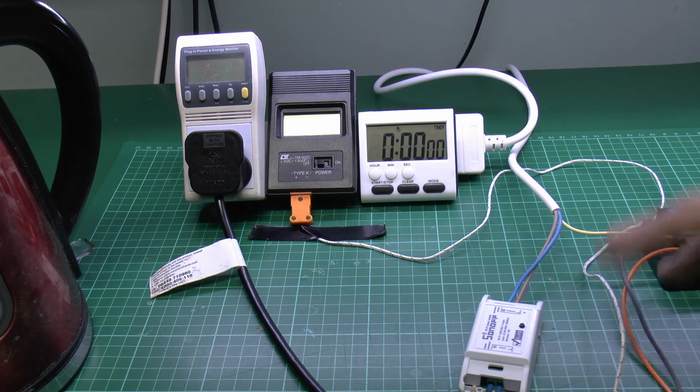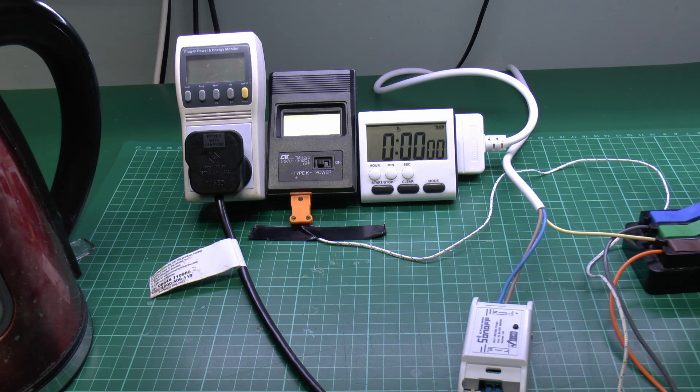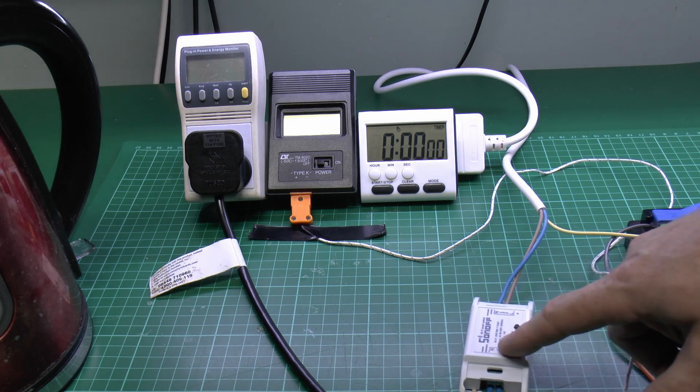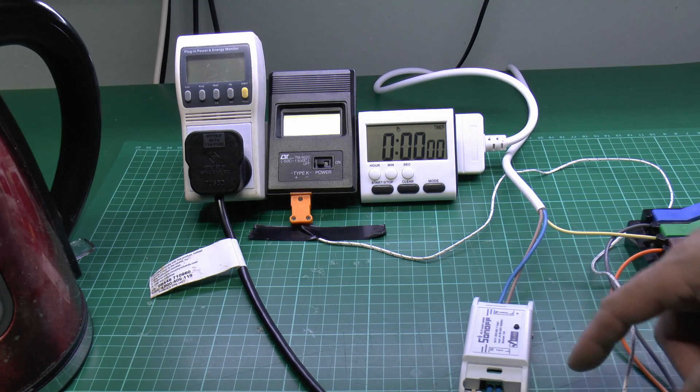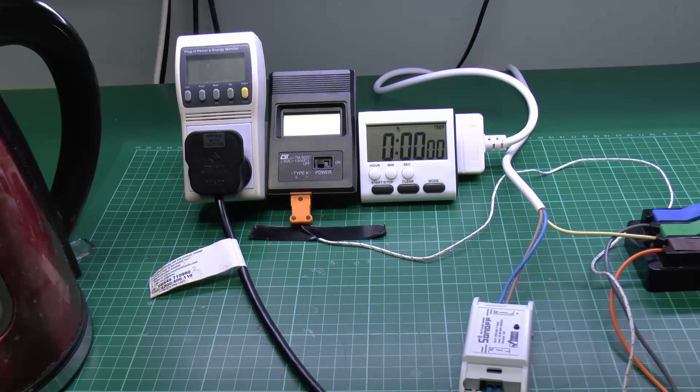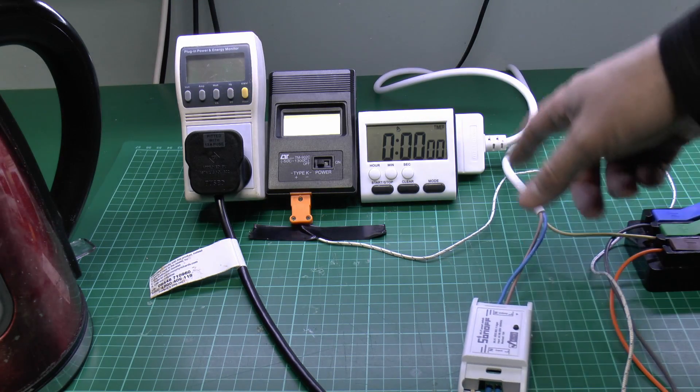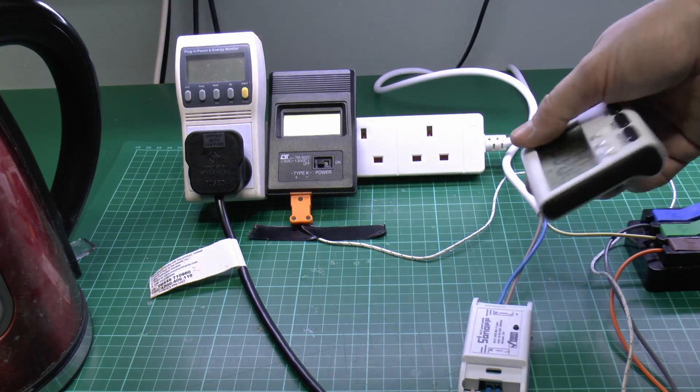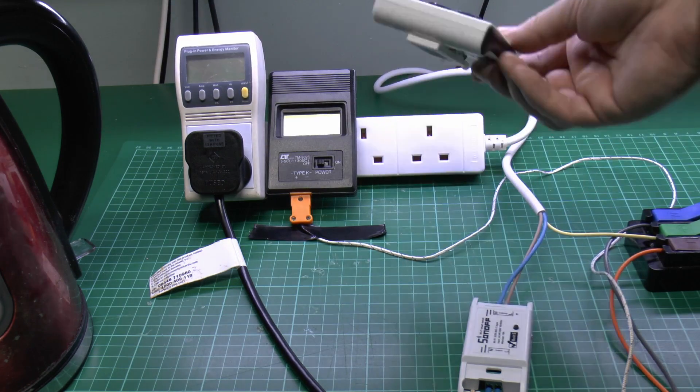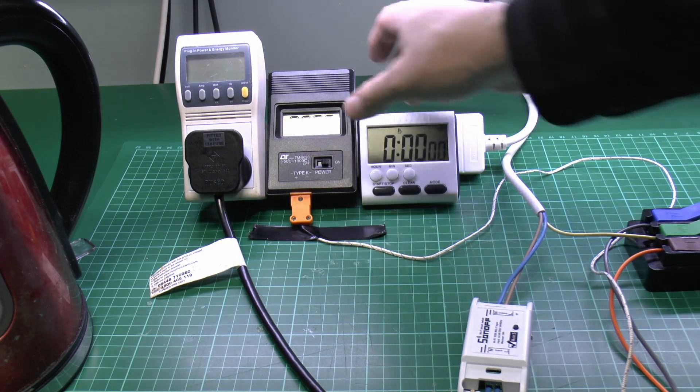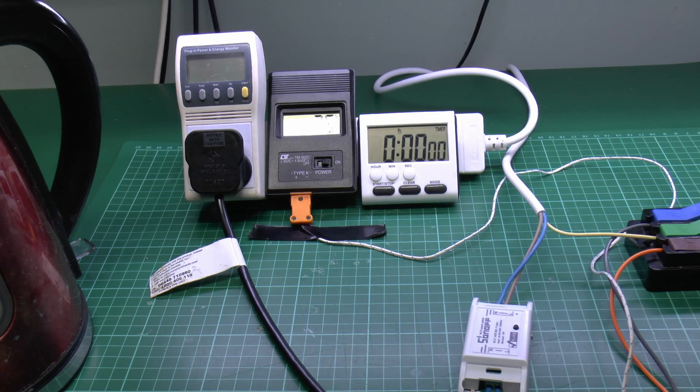Now here's the test arrangement. Power coming in here on this connector block, line and neutral just go into the device here. And the earth actually comes directly there because, as we saw previously, there's no earth connection or pass-through for that. Output on the line and neutral just goes into this extension block here with the four outlets. Kettle plugs in at the end here through this power monitor so you can see how much current is being used. Timer here to see how much time has elapsed. And of course the temperature here in the middle, which I'll just turn that on, and that will just show the temperature in degrees centigrade, so about 25 at the moment.